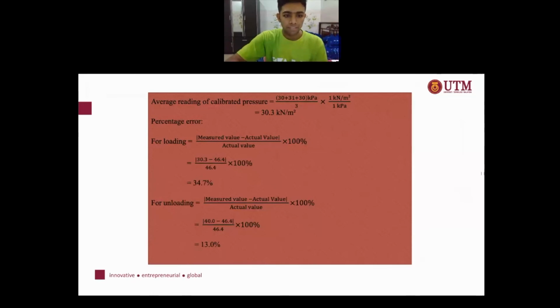And then we find the average reading calibrated pressure, and when we calculate that, we do change the unit. Then we got 30.3 kilonewton per meter squared. Last but not least, we find the percentage error for loading and unloading, and both using the formula measured value minus actual value divided by actual value times 100%. For loading, we got 34.7%. For unloading, we got 13.0%. That's all. Thank you.